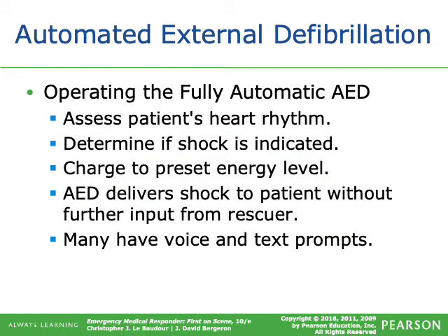Operating the fully automatic AED: it is going to assess the patient's heart rhythm. It's going to determine if a shock is indicated. It's going to charge to the preset energy level. There's nothing you have to do with that. The AED is going to deliver a shock to the patient without further input from the rescuer. Many have voice and text prompts, so they'll tell you exactly what to do and when to do it.